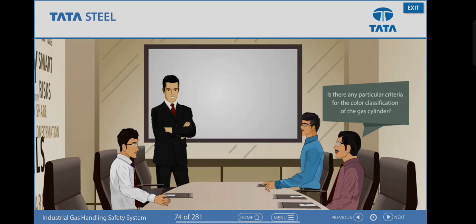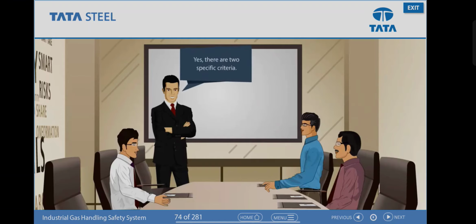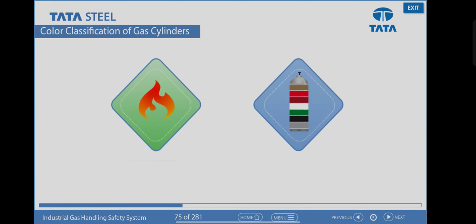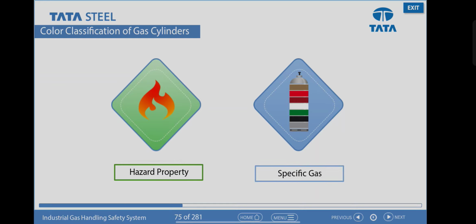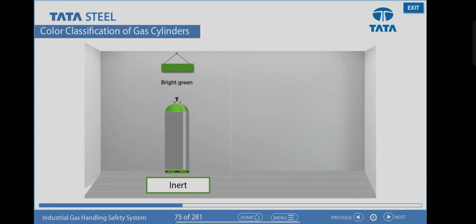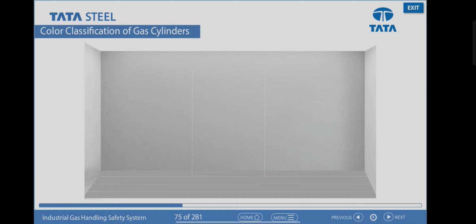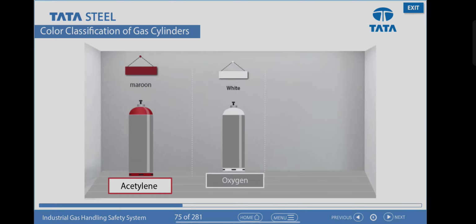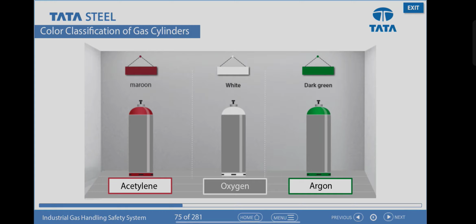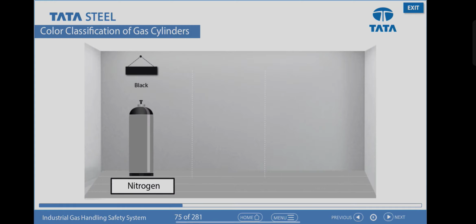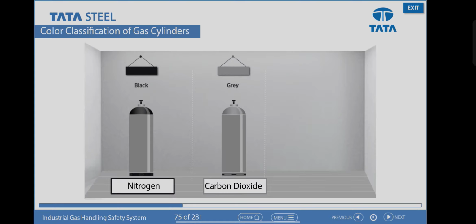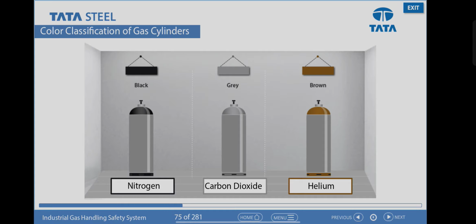Is there any particular criteria for the color classification of a gas cylinder? Yes, there are two specific criteria. Color classification of gas cylinders is done either by hazard property or by specific gas. When classified by hazard property, bright green indicates inert gas and red indicates flammable gas. When classified by specific gas, maroon indicates acetylene, white indicates oxygen, dark green indicates argon, black indicates nitrogen, gray indicates carbon dioxide, and brown indicates helium.